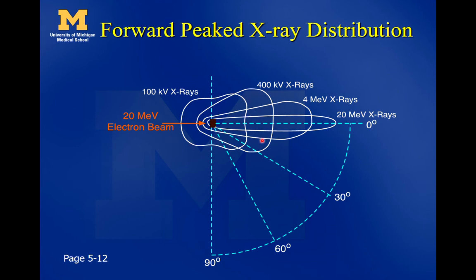This is basically how we get our unflattened beam in the linac. As the electron beam hits the target, the high-energy x-rays are mostly going forward, while the low-energy ones spread out more evenly. We end up with an unflat beam, and in the middle part of the x-ray beam we get more high-energy x-rays compared to other parts of the beam.